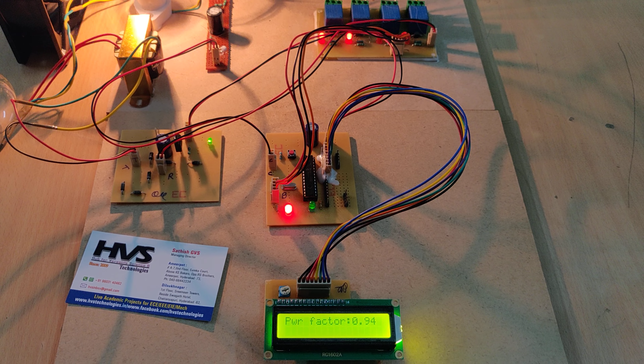So it drops to 0.82, and automatically it will be corrected by adding 2 relays - meaning by switching on the 2 relays, 2 capacitors will be added for a maximum duration of 1.5 seconds. We can see the light keeps blinking, which indicates the controller is processing the input modules and controlling the output modules.